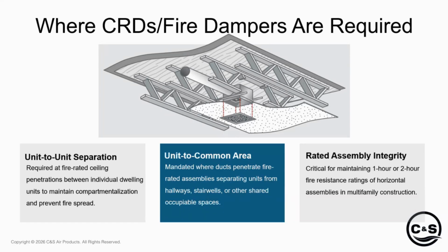Just circling back on where they're required. I've mentioned it a few times, but unit to unit separation, unit to common, so common areas, the bedrooms, the bathrooms, pretty much any opening that you have in an apartment complex where you're exposing the wood truss construction in between floors or up at the roof, that's where ceiling radiation dampers are required.